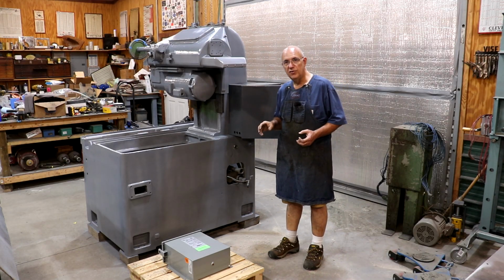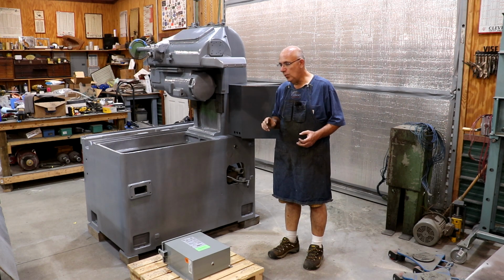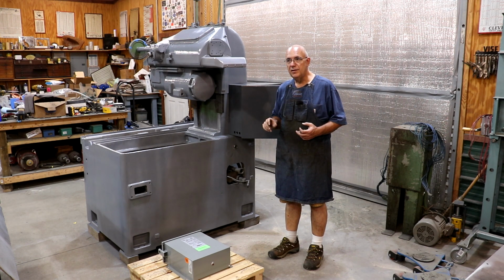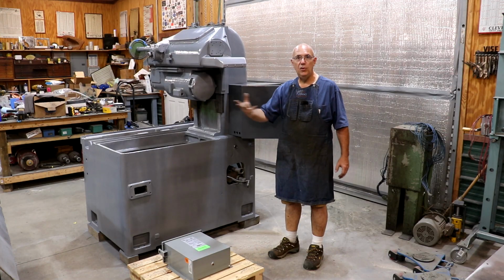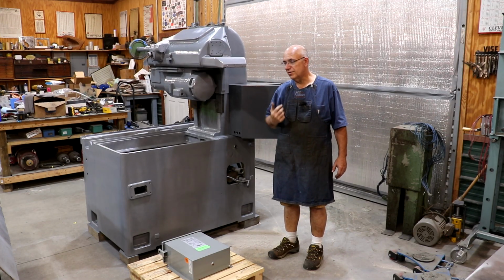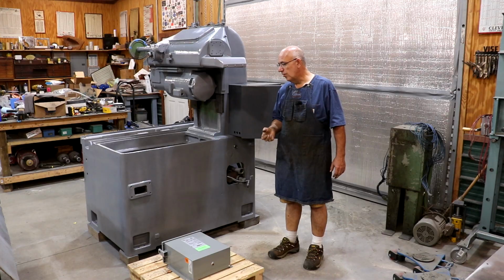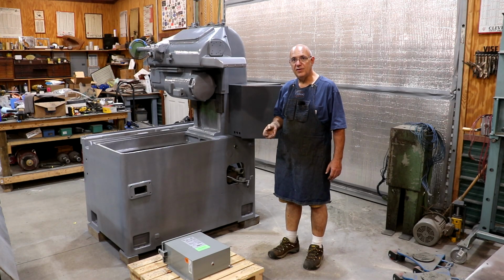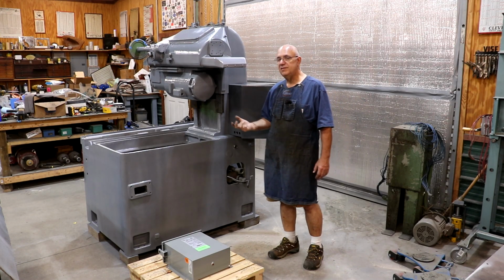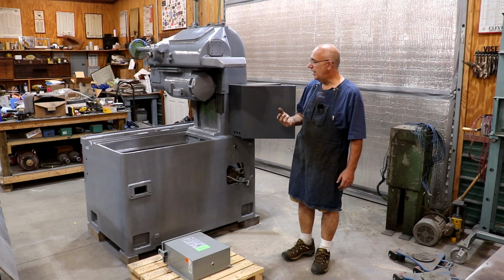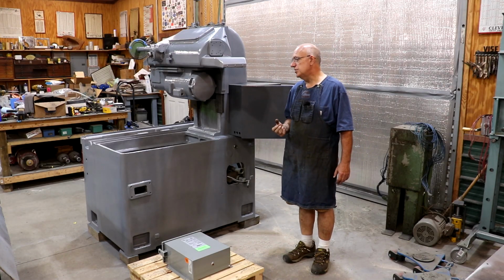However, one of the motors had been rewound at some point, and when it was rewound, the motor shop that did the work didn't pull all 9 leads out - they only had 3 lines coming out. It was wired for 440 volts, and short of having that motor rewound or replacing it, there's no practical way to get it on the low voltage option.